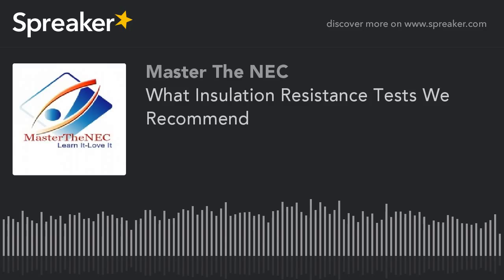Well, in a previous show, I did a little bit of an explanation on insulation resistance testing. I kind of dispelled some of the myths about what values you're expected to see when you go from an insulated conductor to an insulated conductor. I also dispelled the myths about taking connections between an insulated conductor and the earth, which is impossible to get any reliable readings from. You'll get sporadic readings, something you can't really use. And if it was a court of law, I would eat you alive because that information would be thrown out.